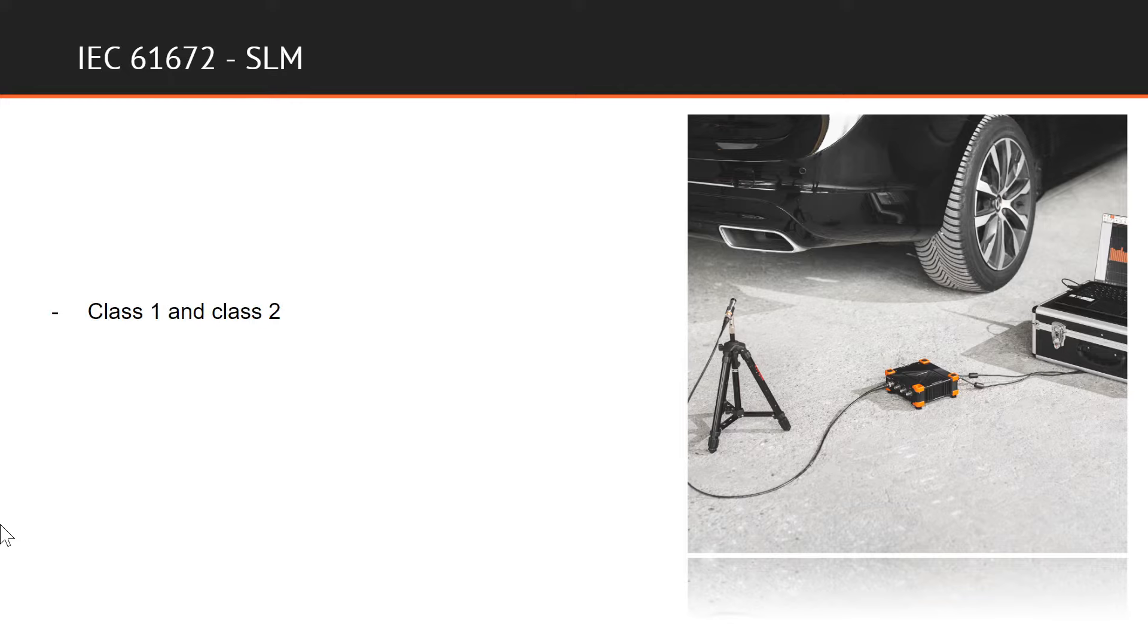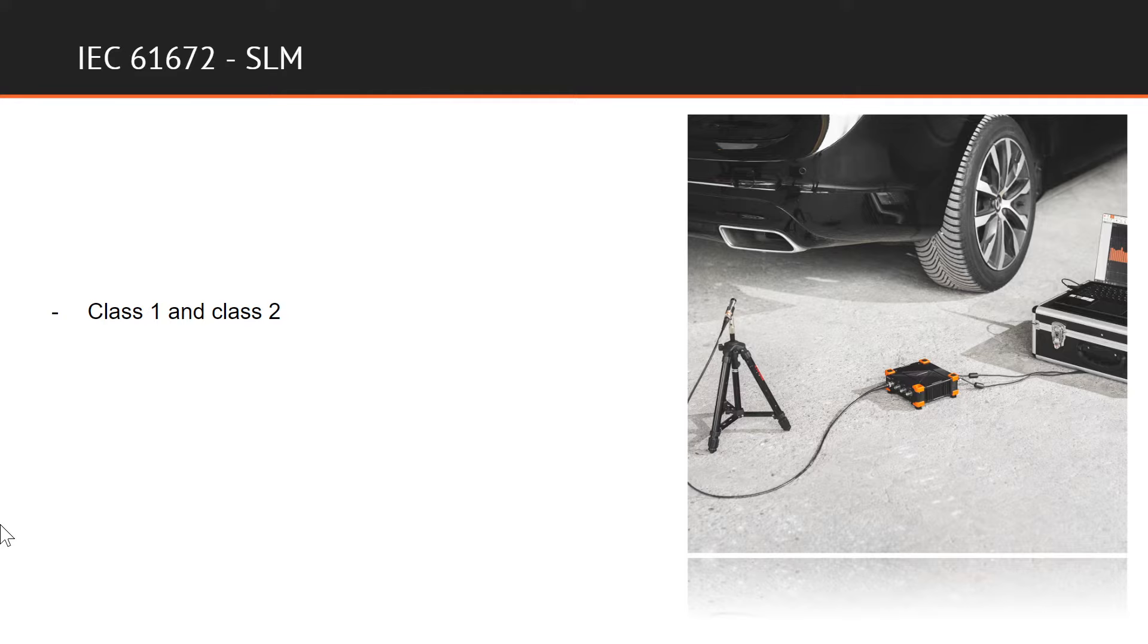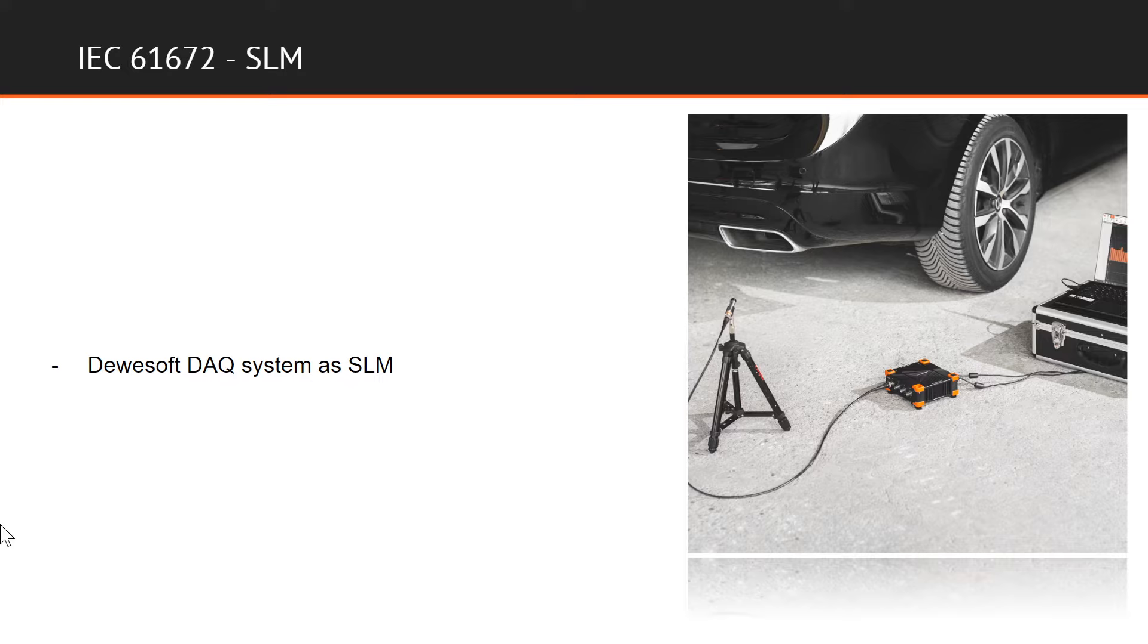Sound level meters are divided into different classes of accuracy, where class one is intended for precision measurements and class two for simple measurements. Approximate accuracy for a sound level meter of class one is 1dB and for class two the accuracy is 2dB. Dewesoft data acquisition systems can be calibrated using the procedure for class one sound level meter in accordance with international standard IEC 61672.